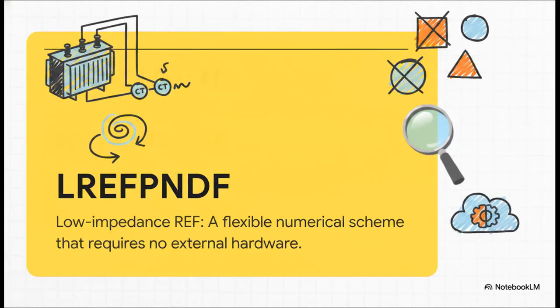First up is LREFPNDF, the low impedance REF. This is a highly flexible, software-driven numerical scheme. What makes this one so appealing is that it's super simple to commission. Why? Because it requires absolutely no external hardware. No stabilizing resistors, no varistors, nothing. It's incredibly clean. It just uses internal numerical algorithms right inside the relay to compensate for equipment variations, specifically when your current transformers, your CTs, don't perfectly match.